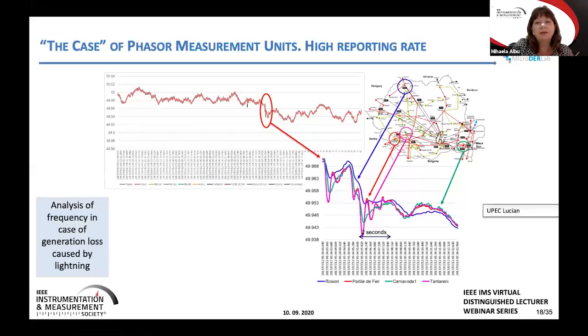The reason I say this high reporting rate was important is that the frequency variation showed higher sensitivity to the generation loss for 2 of the nodes, while the one most distant in geographical terms this time showed much less variation. Practically, it did not record these events.